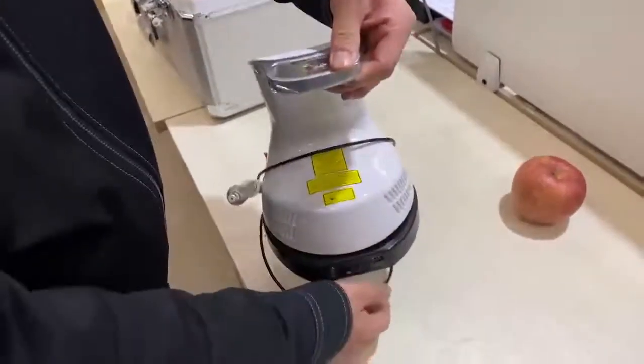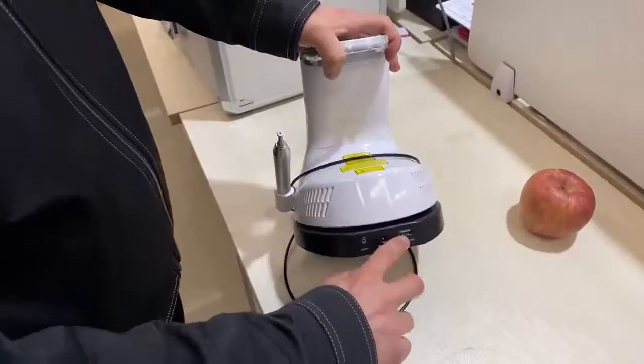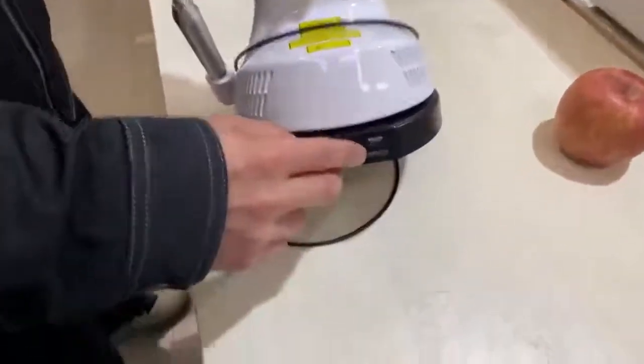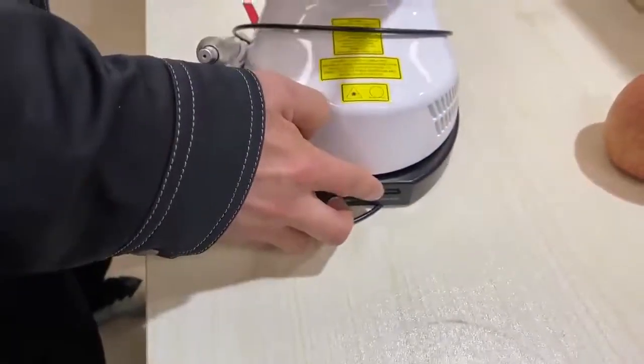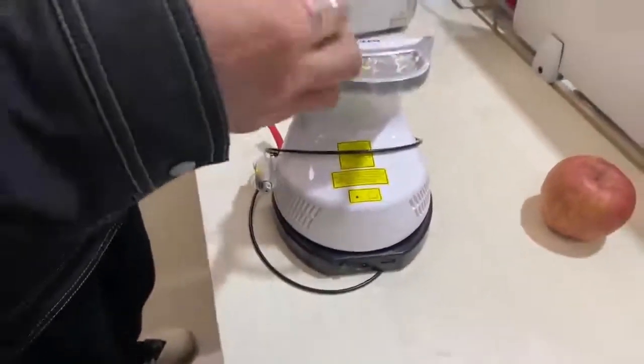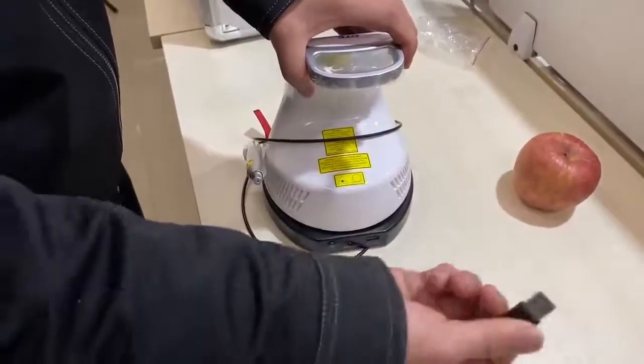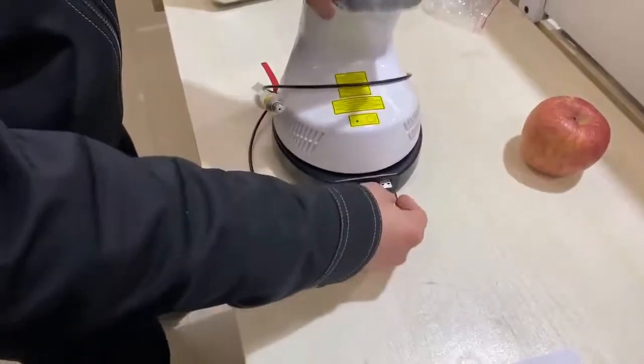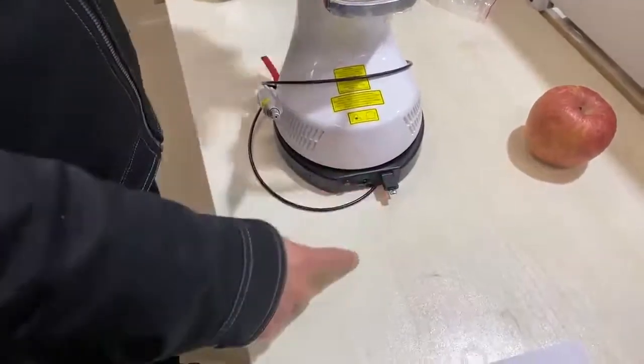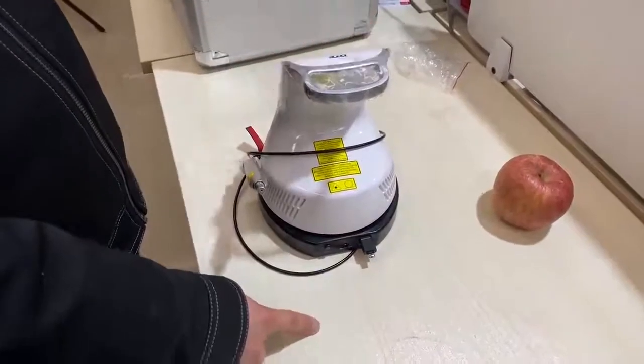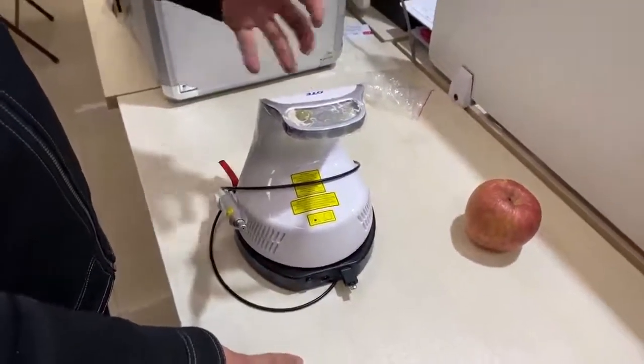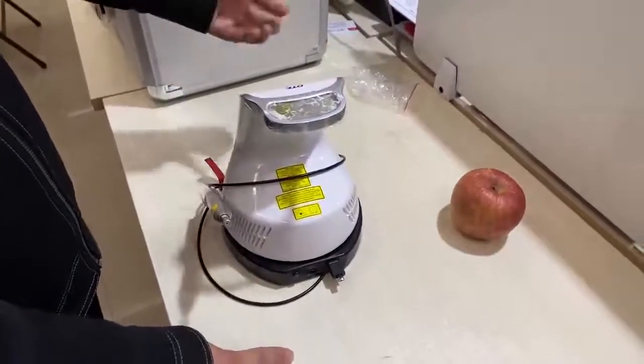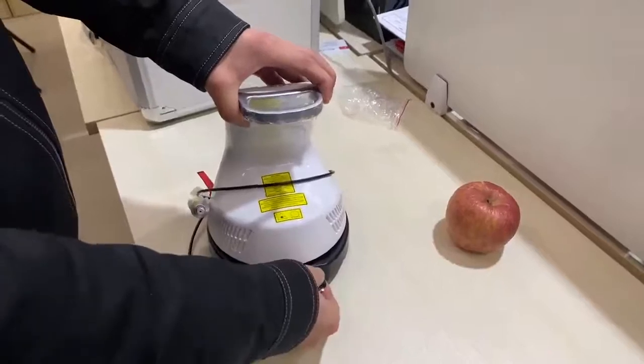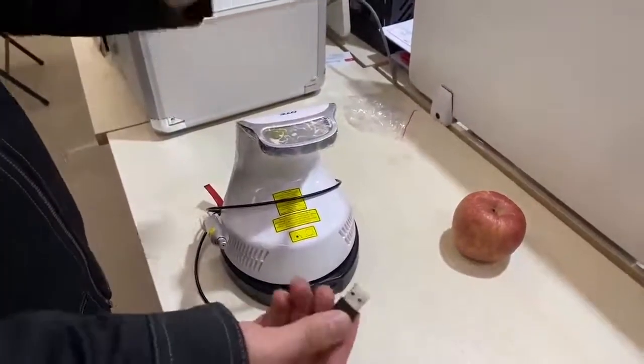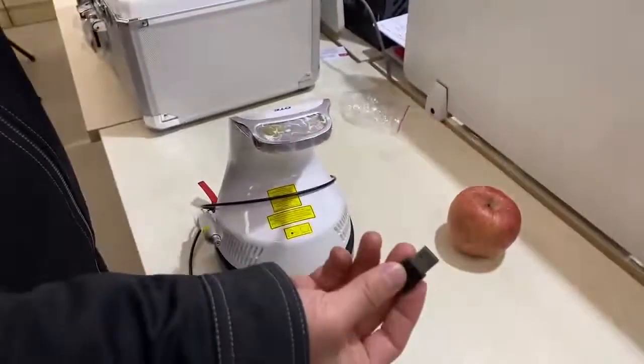And we can see the back side of the laser. So first we can see here is an outlet. It is for an interlock remote control device, and it should be this device you can see here. Sometimes we can put this device inside this remote control interlock, and then we can connect this device into the room electric circuit. And then if someone breaks into the room, it will automatically shut down the device. So this is for interlock remote control, but this is seldom used, so we can ignore this part. Usually we don't use this part.